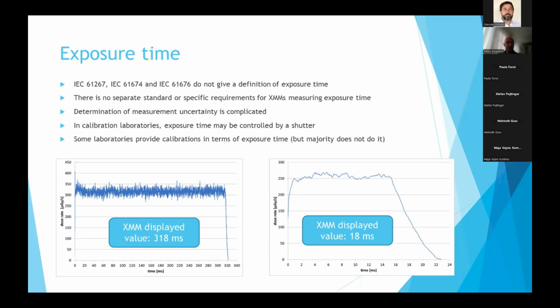So as I said, if you look at different standards, for example, the standard for air kerma measurements, for PPV measurements, or the standard that defines reference radiation qualities, none of them give a definition of exposure time. And also there is no separate IEC standard that gives requirements for non-invasive measurement of exposure time. Because of this, it is not easy to calculate measurement uncertainty for clinical measurements. So maybe you have a calibration certificate and you have the uncertainty of the calibration factor. But of course, there are other influences that can increase measurement uncertainty.